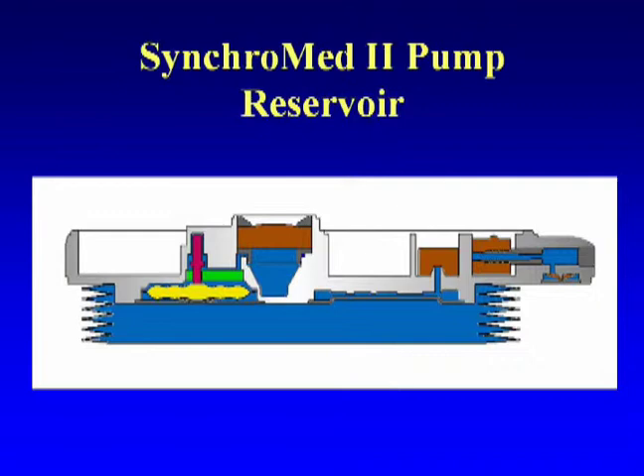This is the SynchroMed II reservoir pump system. Here's the inlet, reservoir, and valve stem. As the reservoir fills, the stem moves down and closes off, preventing any more drug from being put in, limiting overpressure.